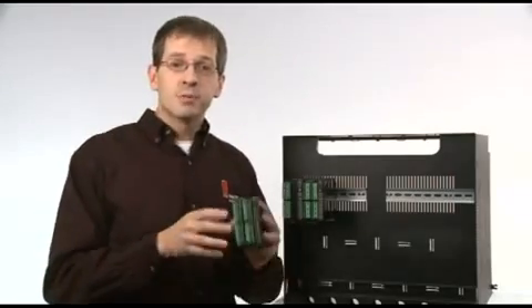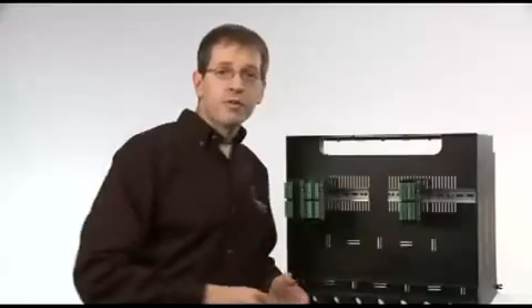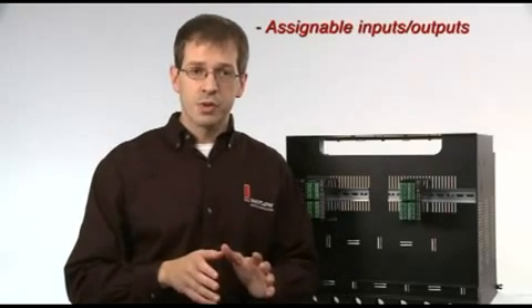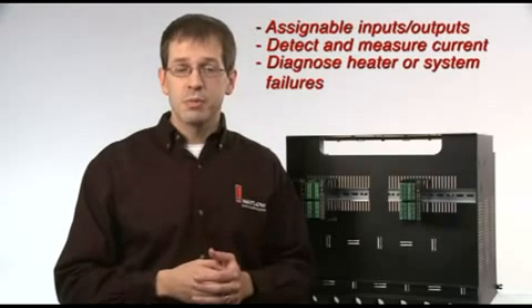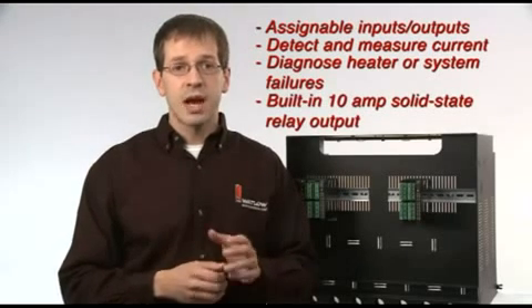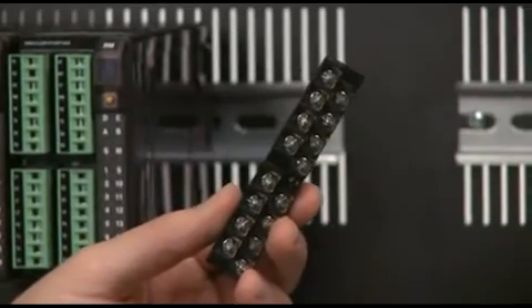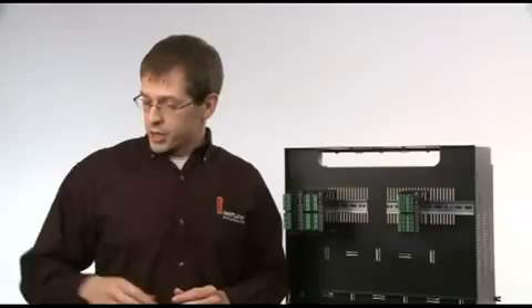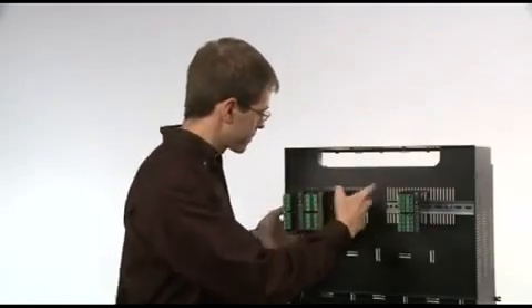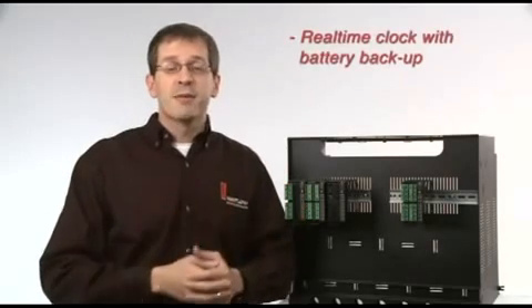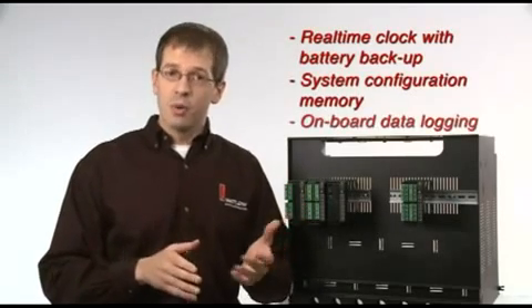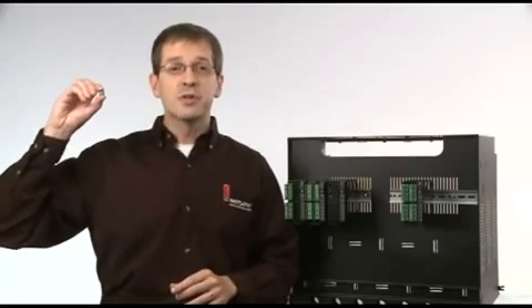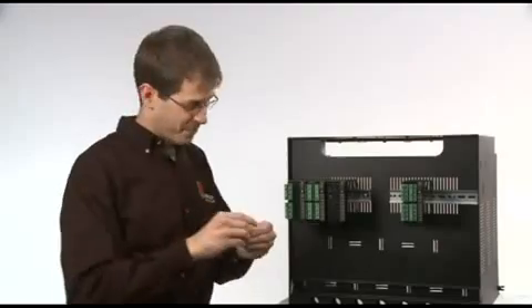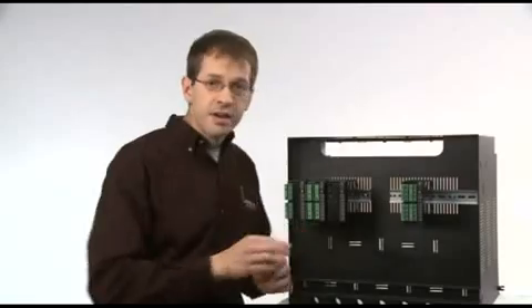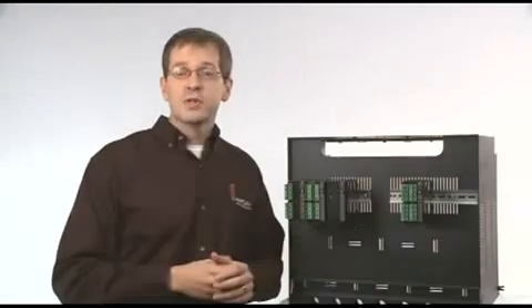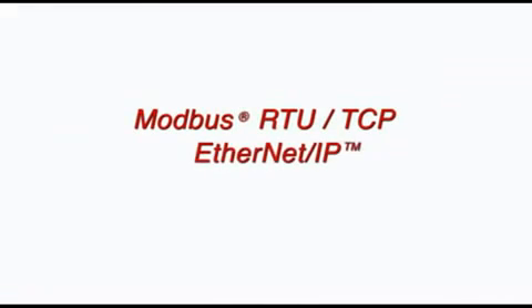Now, the EZ-ZONE RM expansion module provides you with the ability to have assignable inputs and outputs between modules, detect and measure current, and diagnose heater or other system level failures. It also has a built-in high current 10 amp solid state relay output and optional ring lug connectors which may be needed for specific applications. By adding the access module, you can have everything you need: real-time clock with battery backup, system configuration memory, onboard data logging, and an optional removable micro SD memory card. That's not all. There's a built-in USB port and the choice of 3 protocols: Modbus RTU TCP, Ethernet IP, and DeviceNet.